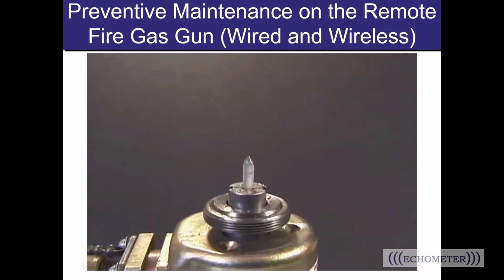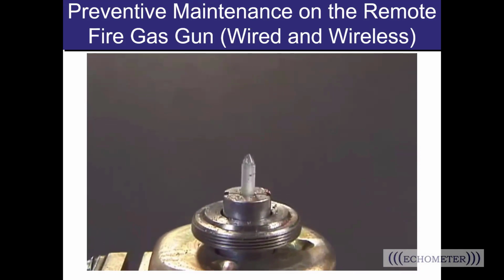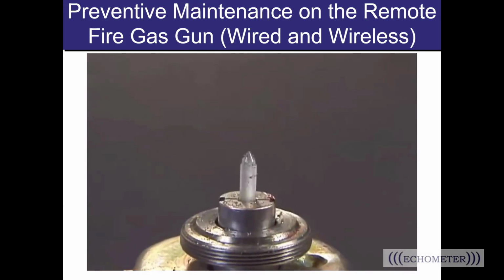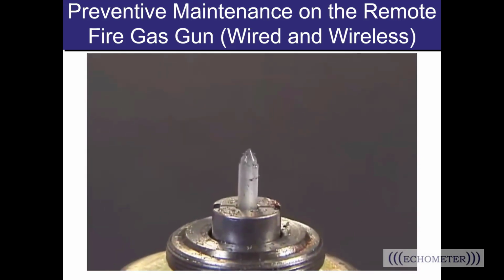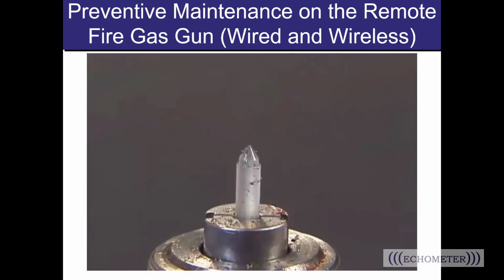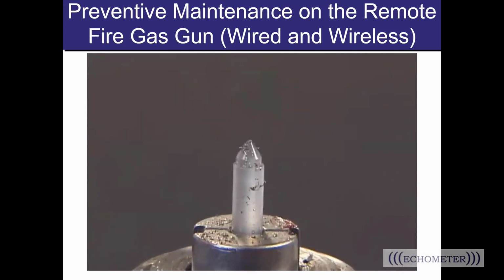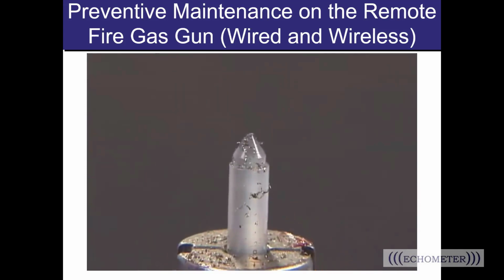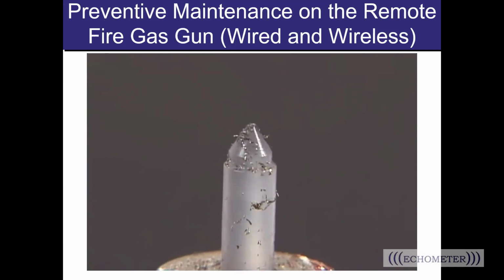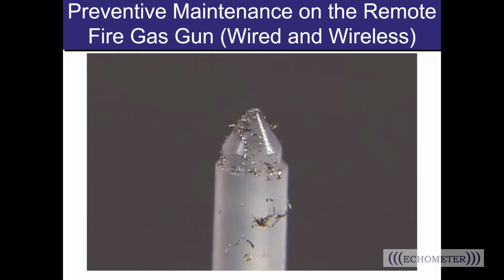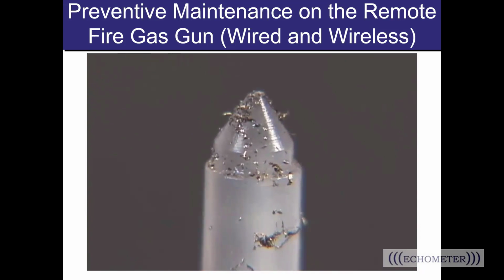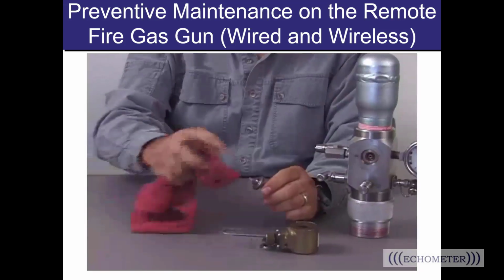So Rusty's showing us where the dart valve is. We've got a great little focus on the dart valve. And so you can see there's just tiny little fragments that get around that dart valve and prevent it from making the seal and doing its job. And so if you've got a dart valve that's dirty, you need to go in and clean it. You can even just use your shirt, just use a rag, something just to wipe off that tip and get it nice and clean.